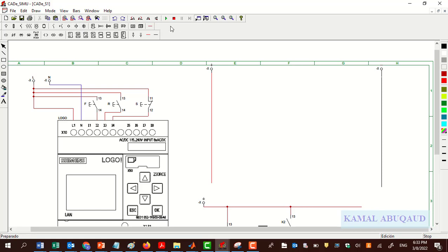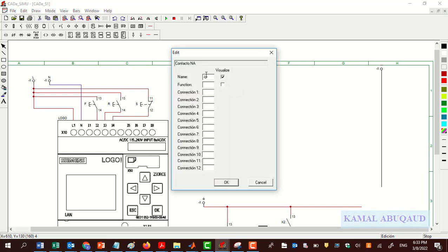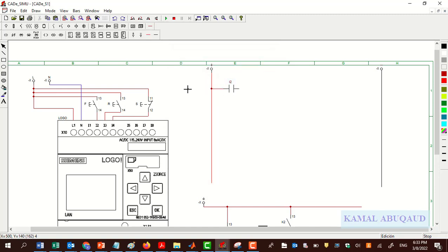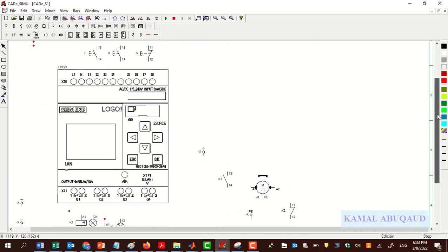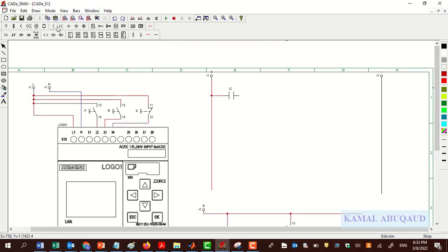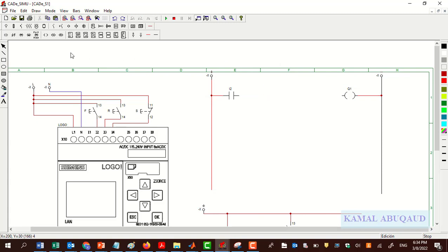Any ladder diagram consists of contacts and coils. Click on Ladder, then select Normally Open Contact. This normally open contact represents the forward push button. According to the circuit, the forward push button is connected to input number two, so I'm going to tell the software that this contact is connected to input number two. I want this input to turn on the first relay coil which is connected to Q1. I add a relay coil to represent the output and rename it Q1.